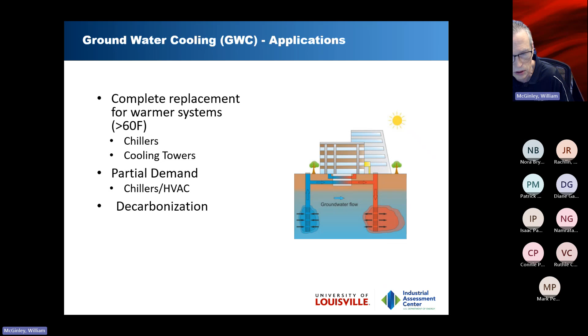So this groundwater cooling can be quite significant. A simple 6-inch well in tandem with another well where we can dump the water back down—you need the tandem setup with the two wells, one source and one sink. That gives you about 100 tons of cooling from that water. So it doesn't take a lot.